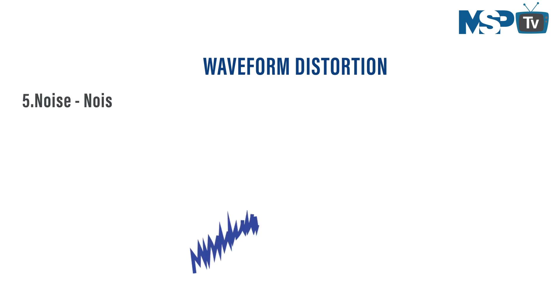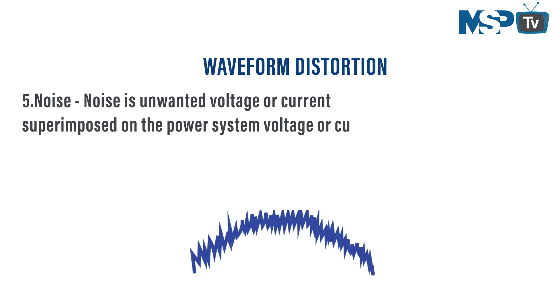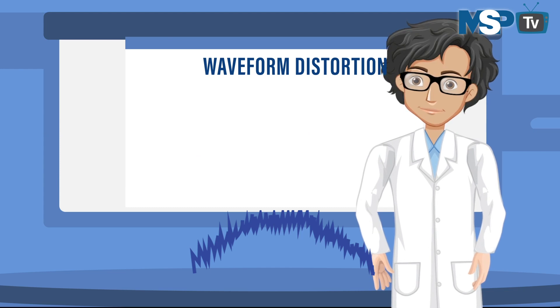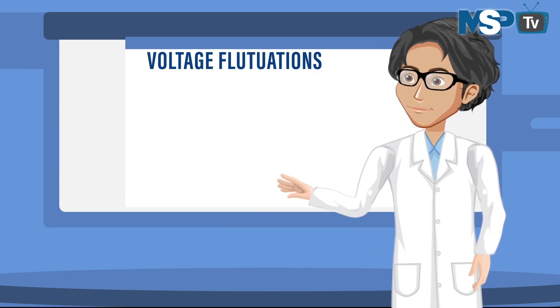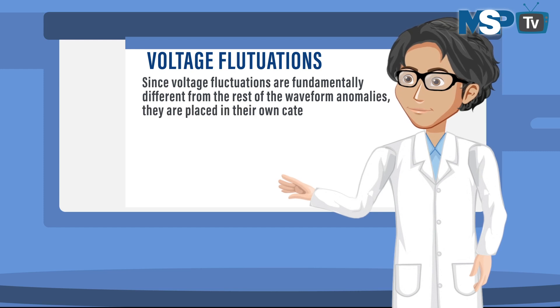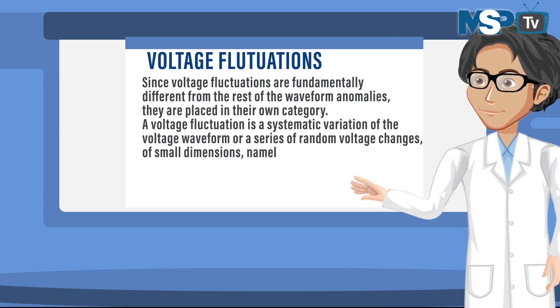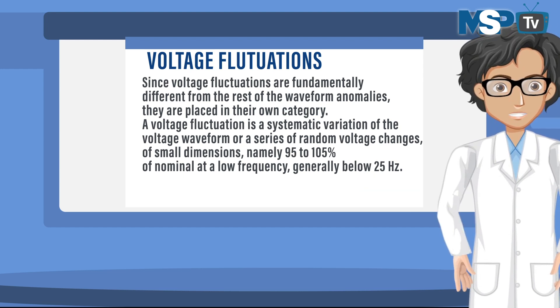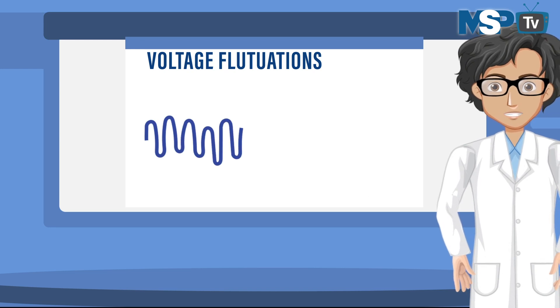The fifth subtype is noise: unwanted voltage or current superimposed on the power system waveform. Noise can be generated by power electronic devices, control circuits, arc welders, switching power supplies, radio transmitters, and so on. The sixth type of power problem is voltage fluctuations. Since voltage fluctuations are fundamentally different from the other waveform anomalies, they are placed in their own category. A voltage fluctuation is a systematic variation of the voltage waveform or a series of random voltage changes of small magnitude — namely 95 to 105 percent of nominal — at low frequency, generally below 25 Hz.